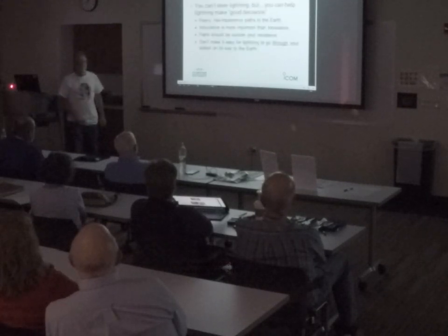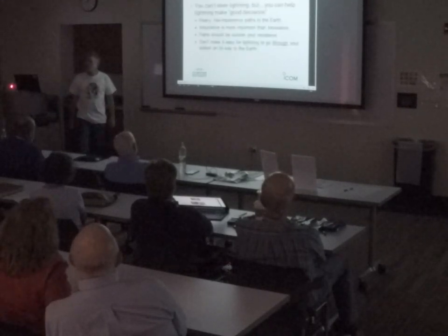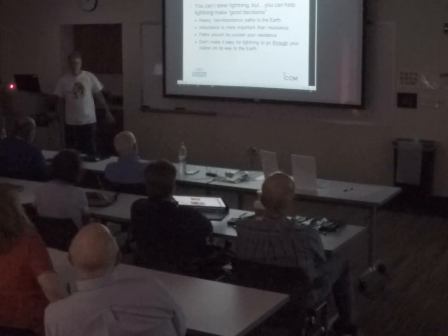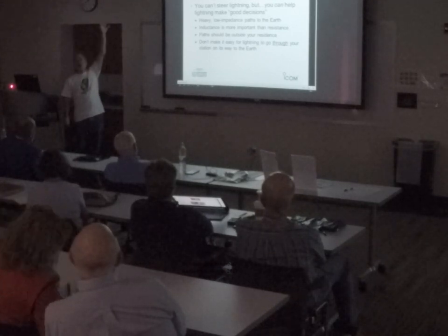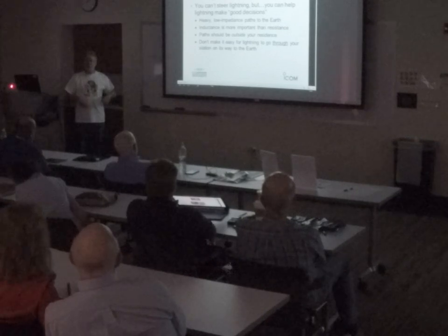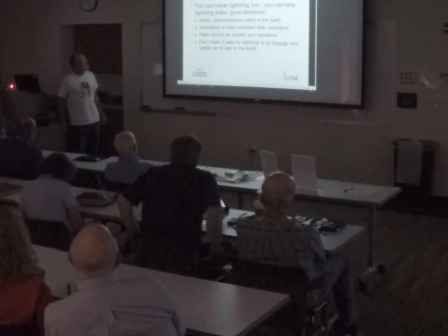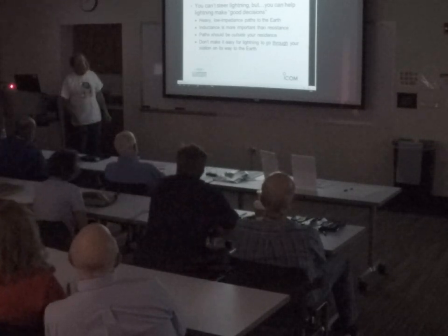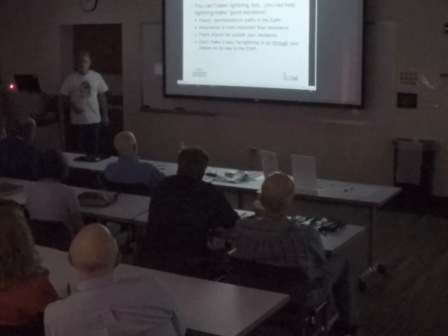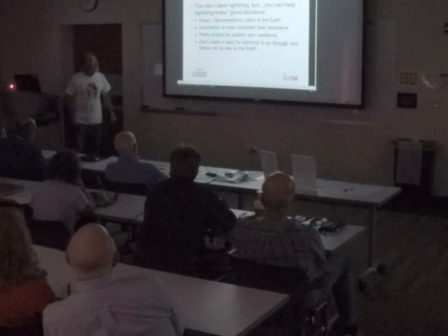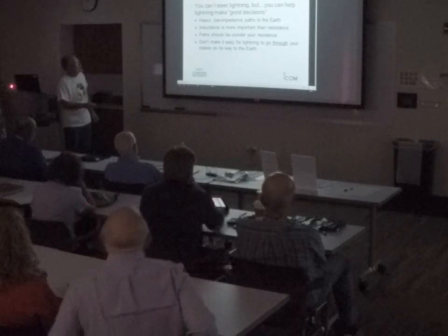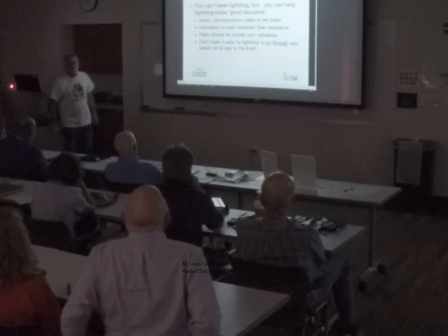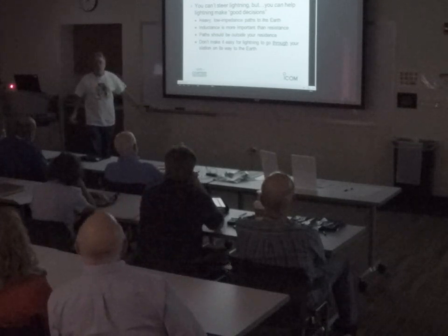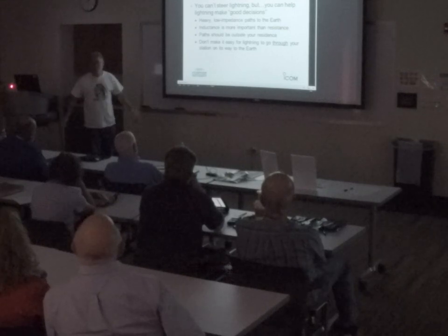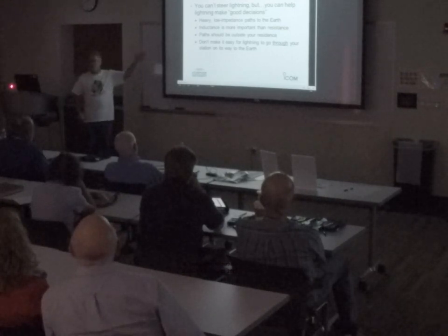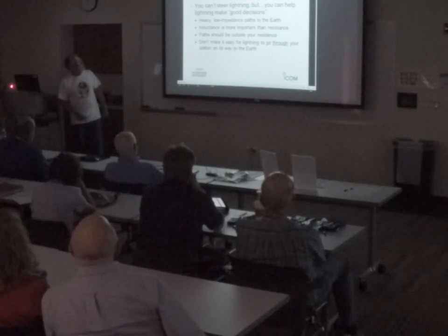Lightning protection - you can't steer lightning. It doesn't even know about you, okay? It's coming from thousands of feet up in the air, and it's going to go where it wants. So you can't really steer it, but you can help it make good decisions. What you want is a heavy, low impedance path to the earth - that's where it wants to get to. Help it get there. Give it a good, solid, robust path.